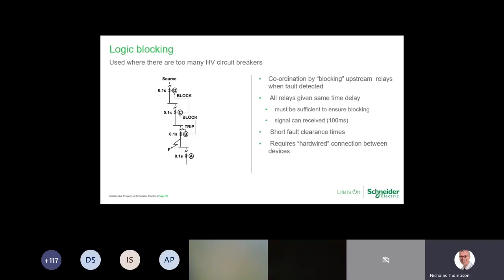So the principle is that A won't see the fault, B and C and D will see the fault. Because A hasn't seen it and B has, B will then send a blocking signal to C, and then C will send a blocking signal to D. D and C will then remain closed, and B will trip. That's the overall principle of it. But you will need to hardwire each of the protection relays.